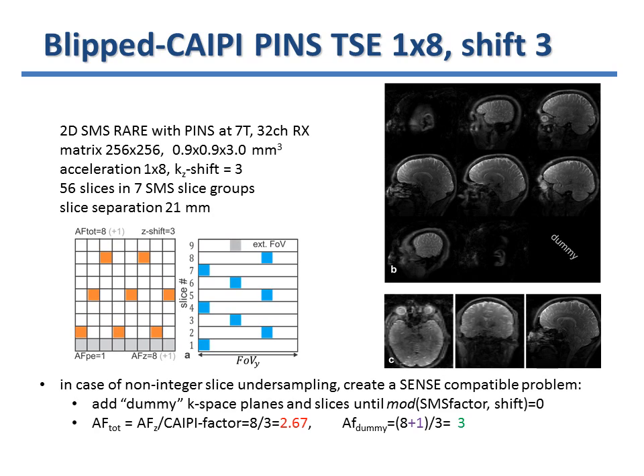This is an example for multiband factor 8 and CAIPI shift of 3, with no additional in-plane acceleration. These parameter choices highlight a more technical aspect of the SENSE implementation: the k-space-based sampling pattern must allow for a periodic extension along all dimensions in order to result in distinct peaks in the image domain. For 8 slices and CAIPI factor 3, this is not the case. Adding a dummy slice creates a SENSE-compatible reconstruction problem, and the extra slice is removed in a post-processing step.